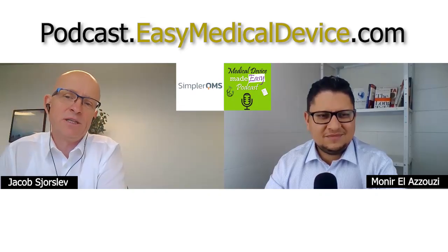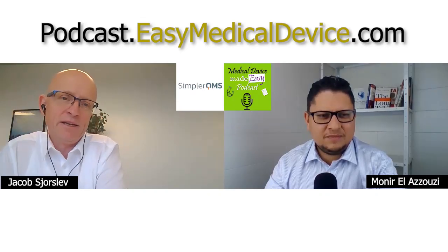I can actually tell you that I was with one of our customers last week, where they said, well, we are getting audited. And I was available at the time, and 20 minutes into the audit, they came for me saying, well, they want to see proof of validation. And I say, okay, that's no problem. So the first thing she asked for was the certificate, then she wanted to see the report, then she wanted to see the validation plan.